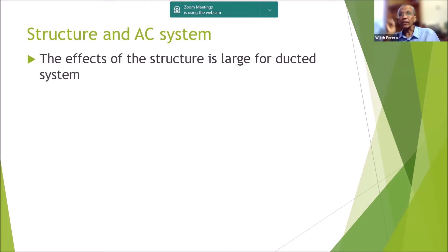Because we do need adequate space to locate the air distribution ducting. Now, this is where we run into major difficulties because these monsters are not small at all. They're big because they are transporting air. So we need a lot of space. Generally, the depth of these distribution ducts is around 400 to 450 millimeters, or maybe 350 to 450 millimeters, which is quite big when it is the depth between the soffit to the ground below.